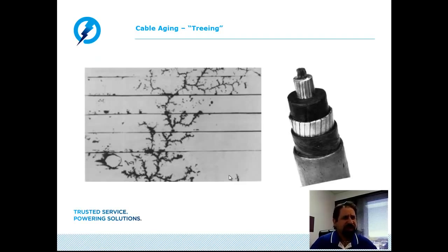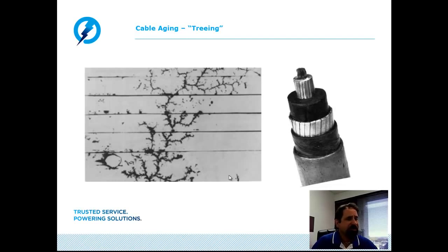In the case of extruded dielectric, the treeing is a result of water ingress and contamination — referred to as a water tree. In laminated cables, the most common cause of the treeing effect is the drying of the oil and burning of the insulating layers of paper. As the insulating layers of paper burn, they leave behind carbon deposits, which are conductive. Over time, as the papers burn and leave behind carbon deposits, a conductive path forms through the insulation, causing cable failure. This type of treeing is referred to as a carbon tree.